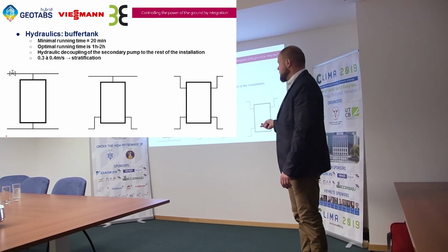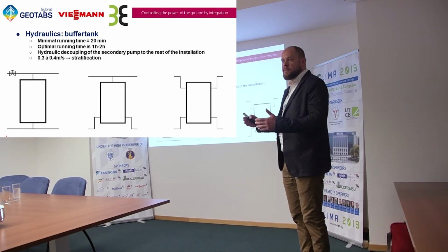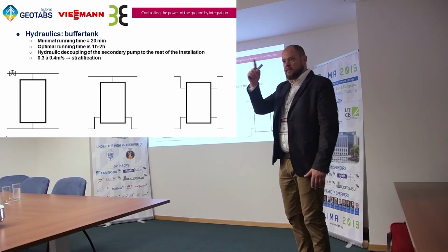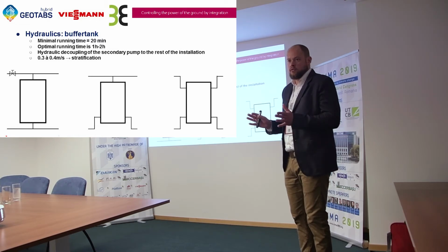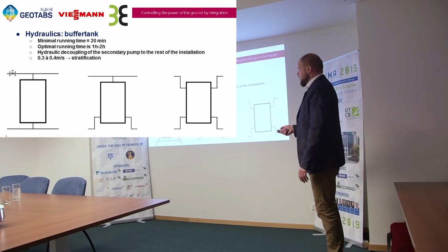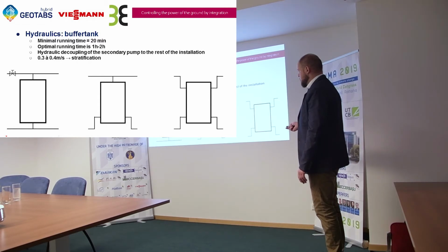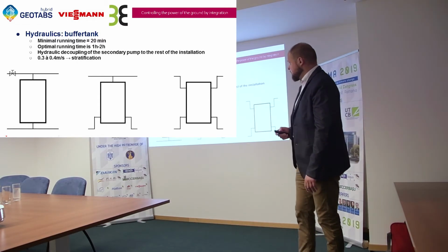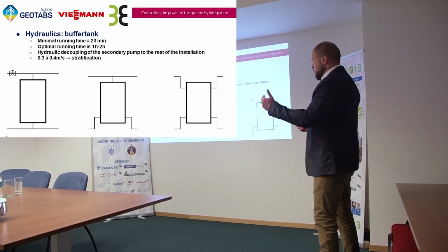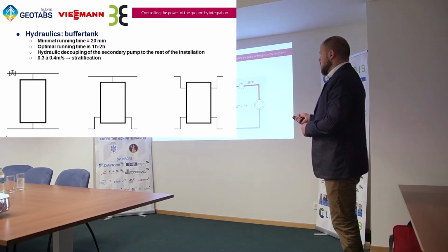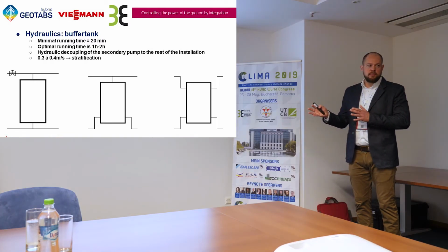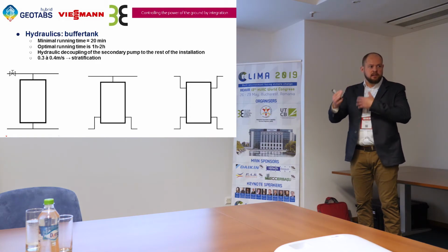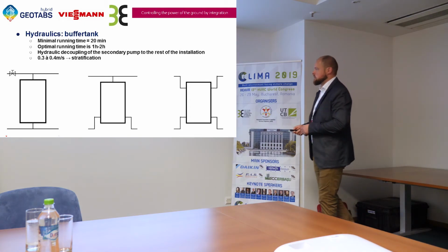So when the temperature sensor is sitting inside of the buffer tank and it's on temperature, the heat pump won't switch on. We have just a flow through the evaporator, but the heat pump thinks, oh, the buffer is on temperature, I have to do nothing. So then we have to add a valve which regulates the pressure drop on this side, or we use this system where all the return water has to pass through the buffer tank, and so it will discharge the buffer tank correctly. Another thing to mention is that the speed at which we enter the buffer tank has to be lower than 0.3, 0.4 meters per second, because if you go over that speed, we get a mixing inside the tank, and that's not correct.